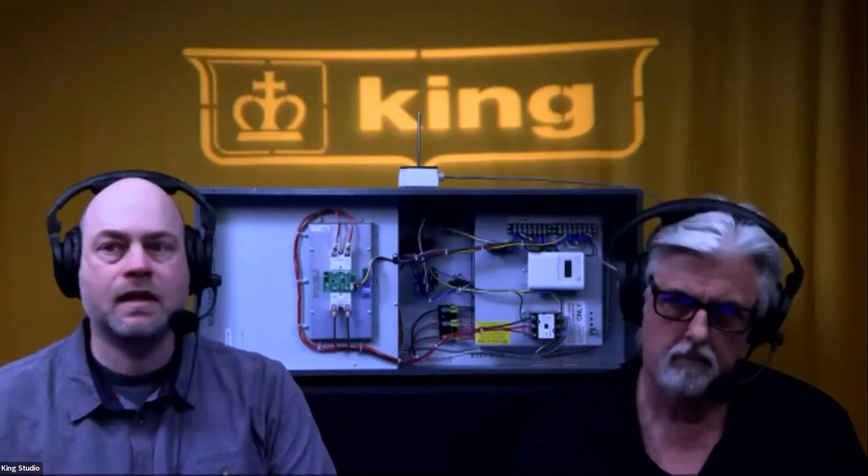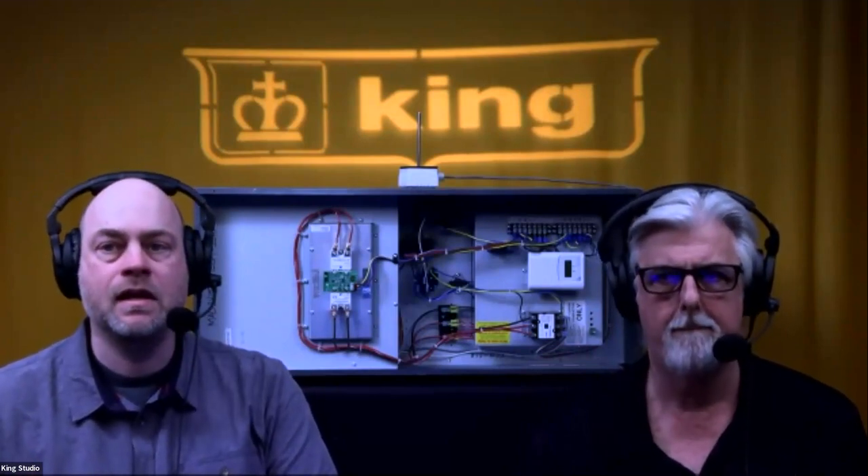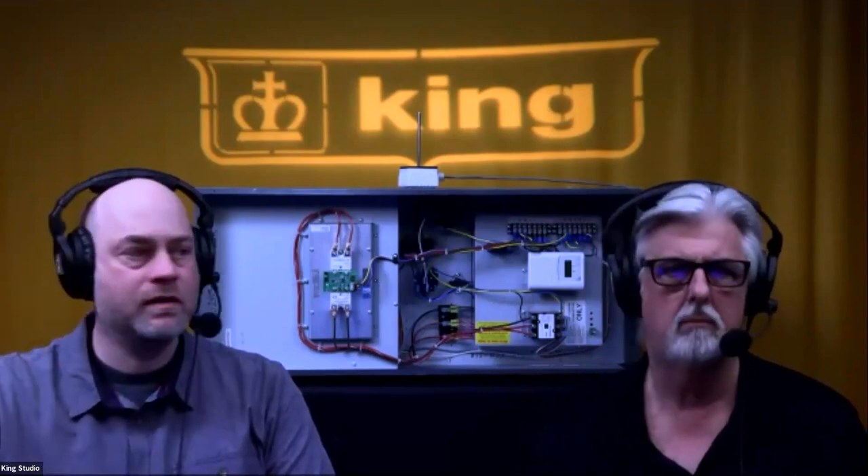That's a serious issue, and it's why we developed the MAU. Our MAU system features an energy-efficient ECM motor combined with a fully modulating heating unit and a fresh air logic control circuit, configurable for just about any application. It's an all-in-one package unit including a duct sensor and proportional control, giving you precision set points to maintain a target inside or duct temperature. A solid-state relay modulates the heat so the room stays within a few degrees of the set point.